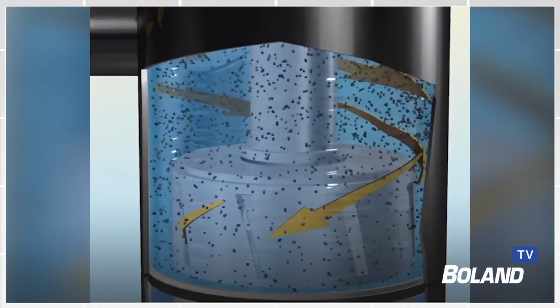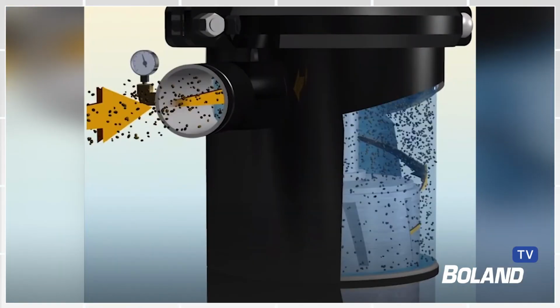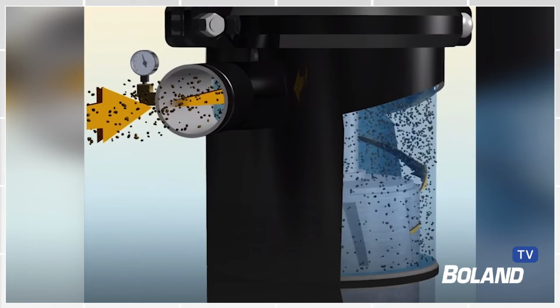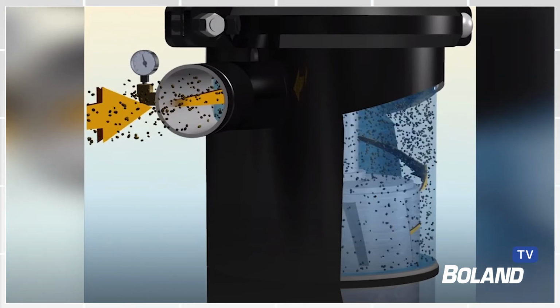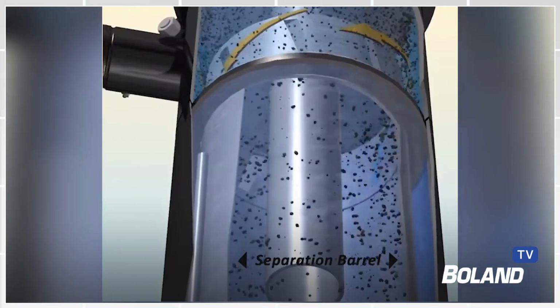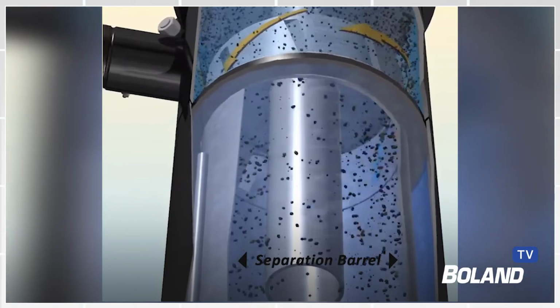Filtration is the third item. Making sure filtration is in play for every system. Closed loops should have cartridge filtration. Cooling tower systems should have some type of centrifugal separator. Lakos separator is one of my favorites, just to get rid of the larger particulates that even with cooling tower cleanings are going to get into the system. Those are typically the 100 micron, 50 to 100 micron rated particles or size particles.